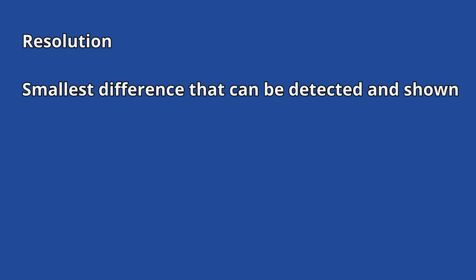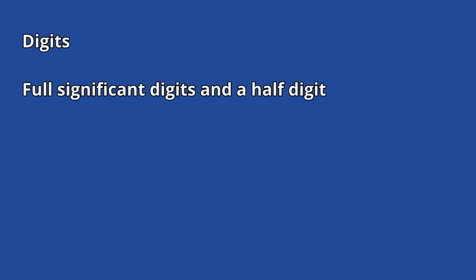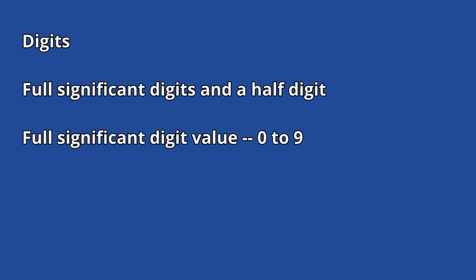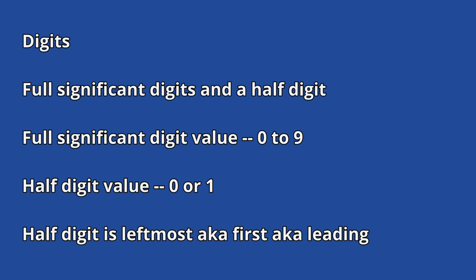Resolution refers to the smallest difference in value that the meter can detect and display. Resolution is commonly specified in one of two ways: counts and digits. Digits is the older approach, where resolution is stated in terms of number of full significant digits along with a half digit. A full significant digit can show a value from 0 to 9, while the half digit can only show the value of 0 or 1. The half digit is the leftmost digit on the display. Yes, it's a little odd, but that's the approach that many manufacturers took when digital multimeters were first introduced.